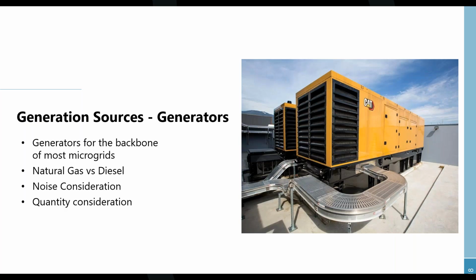Another consideration to keep in mind is noise for generators. Critical grade sound attenuating enclosures can be almost unbelievably quiet, basically whisper quiet from just a few feet away. So the noise pollution problem is always solvable, but it's something that needs to be considered on every project, where you calculate back from what your sound requirement is at the property line or at the nearest sensitive structure, and then you figure out what sound attenuating enclosure level you need for that specific application.